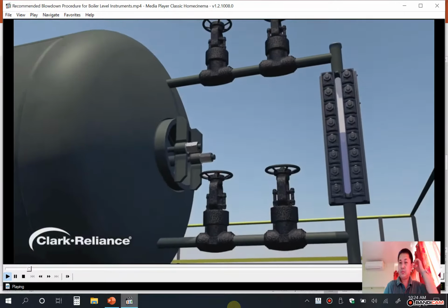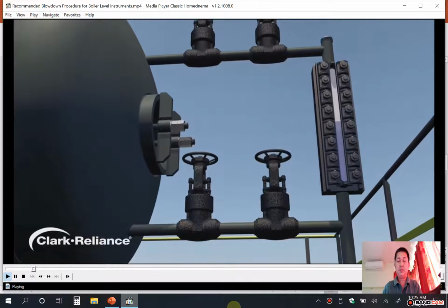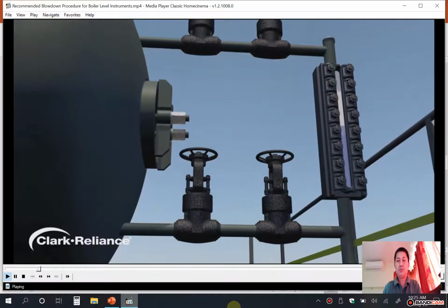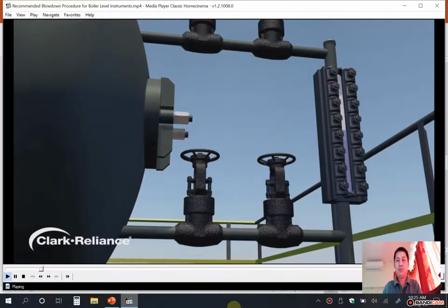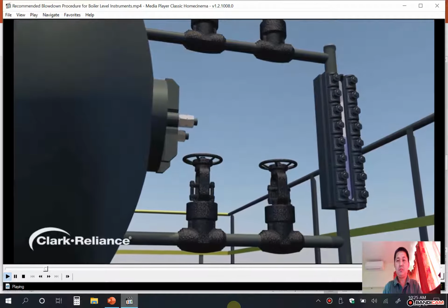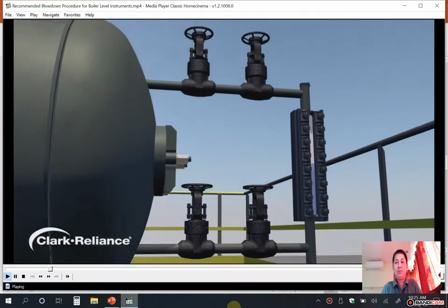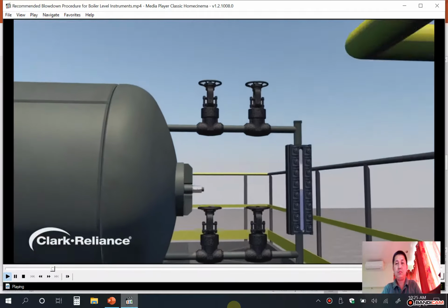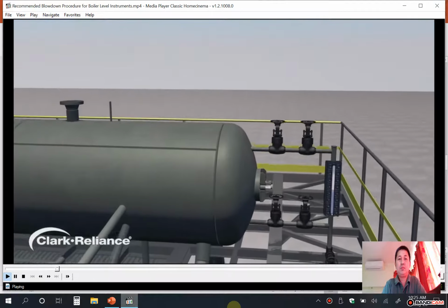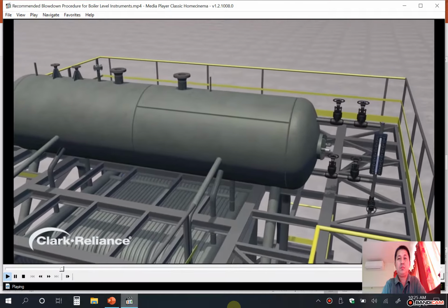The water gauge glass on a boiler enables the operator to visually observe and verify the actual water level in the boiler. However, if not properly cleaned and maintained, a gauge glass can seem to show that there is sufficient water when the boiler is actually operating in a low or low-low water condition. Lack of maintenance may result in a stain or a coating on the inside of the gauge glass where it is in contact with the boiler water, and give the appearance of an incorrect level indication, especially if the drum level happens to be outside the range of the level instrument.